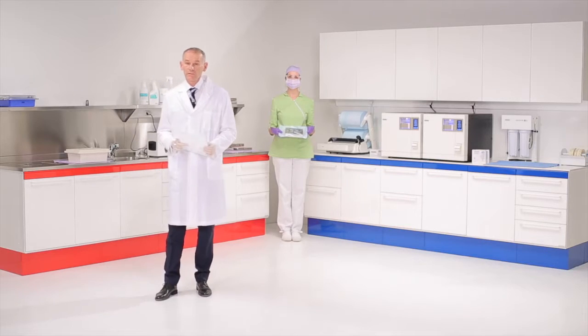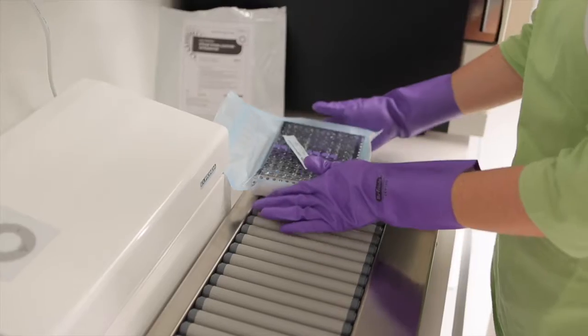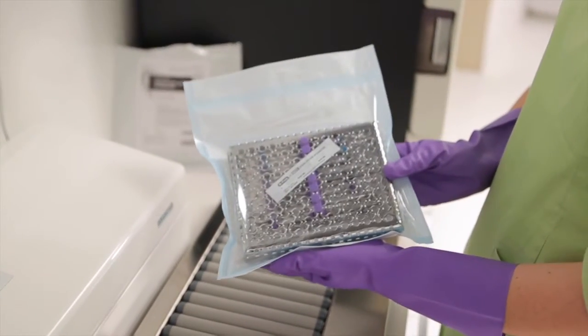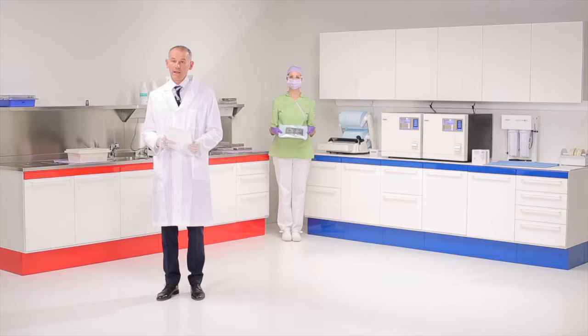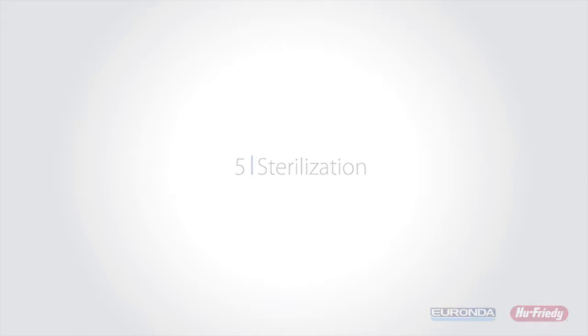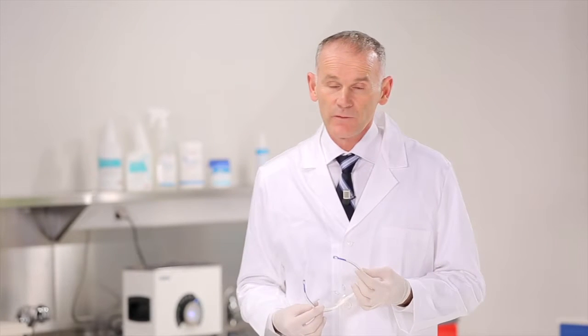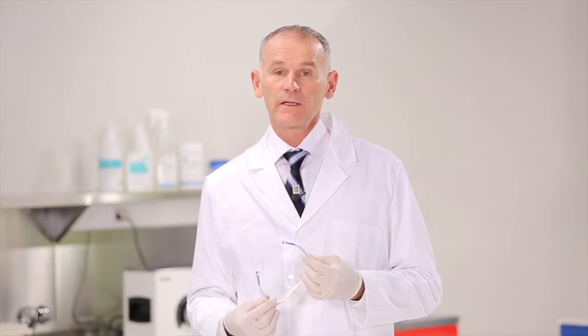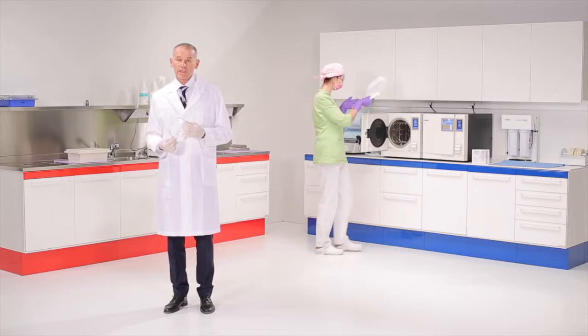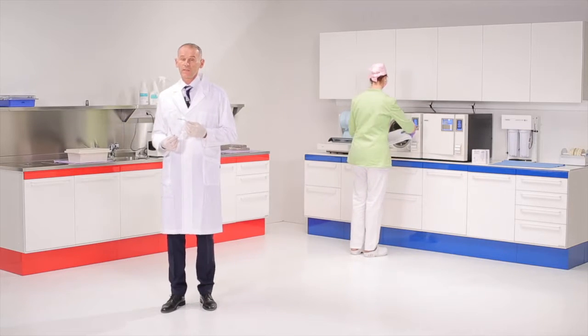A number of rules should be followed with regard to the packaging. The content must not exceed 3/4 of the volume of the packaging. The bag should be sealed with at least 3 centimeters of space between the load and the sealing. Finally, 1 centimeter of space must be left between the sealing and the edge of the paper in order for it to be easily opened at the time the instrument is used. Once the decontamination, rinsing, drying and packaging stages have been correctly carried out, the stage of proper sterilization is reached.